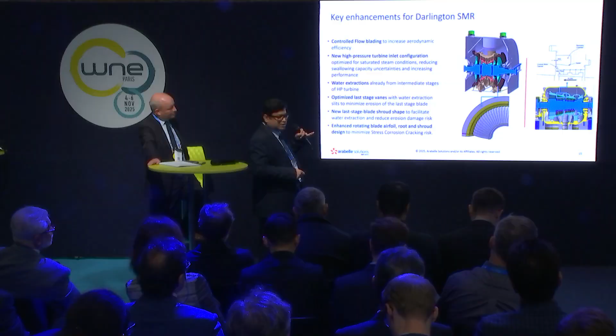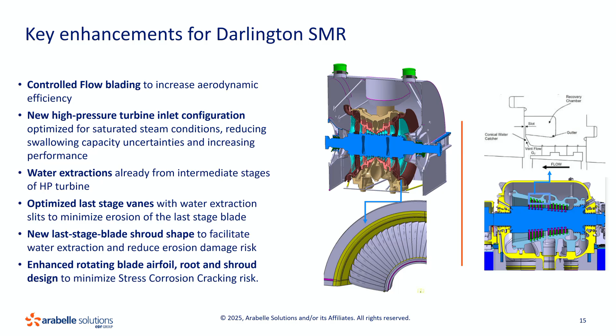Then we have last stage blade shroud shapes. It's a patented technology. It's going under patent, so we cannot disclose much, but that will give more lifetime to the last stage blade again and prevent the leading edge erosion as well as trailing edge erosion. And of course, the L-2 blades, which are a bit heavy. Those are specifically optimized for the Darlington condition to keep the weight less, the centrifugal pull less, and to prevent any risk of damage due to SCC.